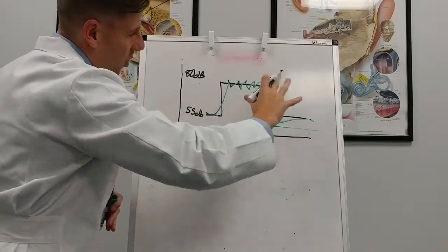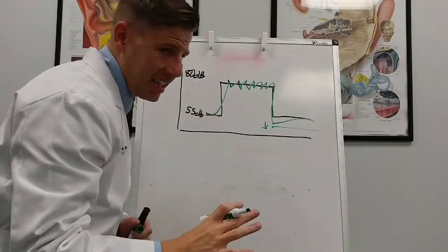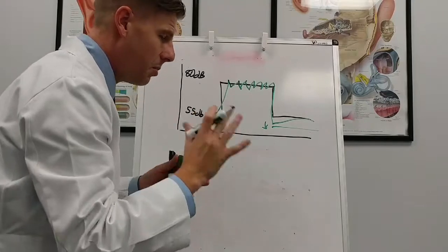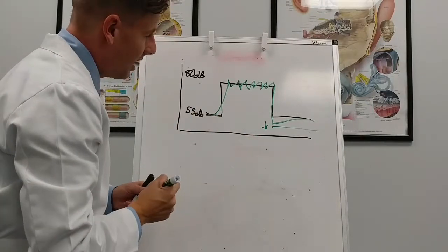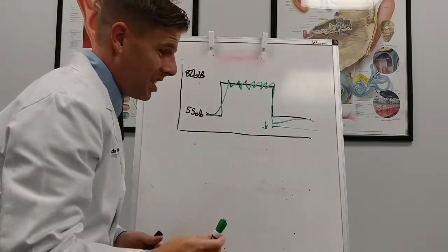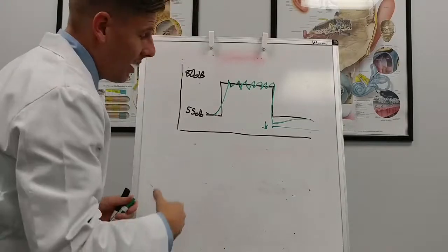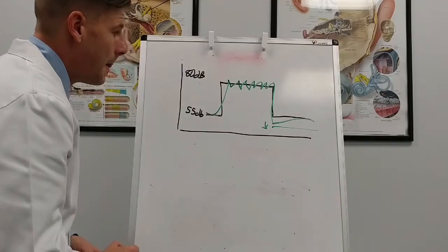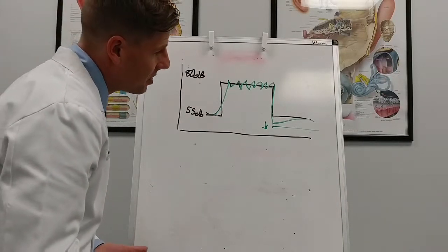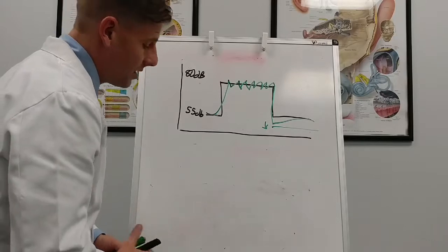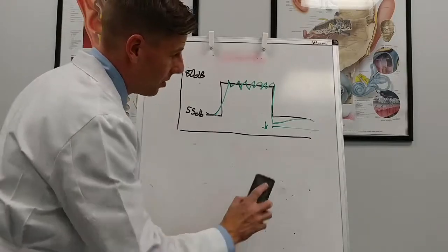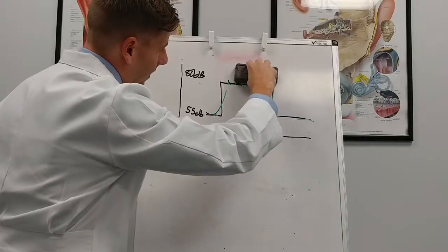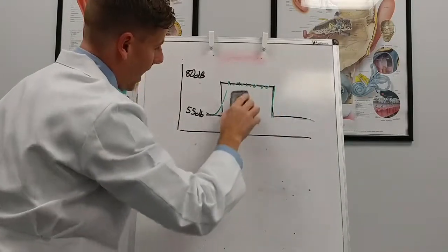And so this whole time it's really trying to fight against this loud sound, which sounds good, but because it gives this pulsating type side effect, it can really steal from intelligibility of speech. And fast compression for a patient that might already be having processing issues, they might be getting older, this is something that will make things very garbled. So, all right, I have a side effect there if my compression is too fast.